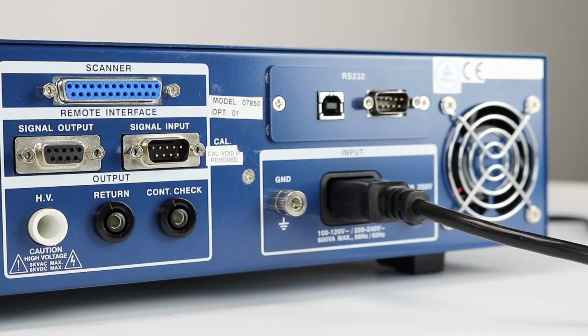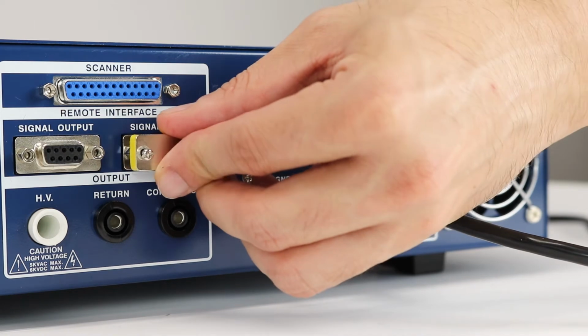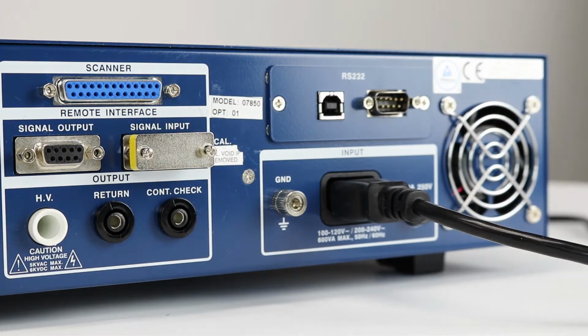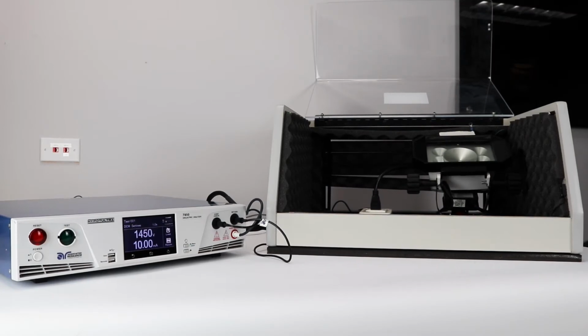Insert the remote interlock key into the signal input terminal on the rear panel. The instrument will not output voltage without this key. This allows the user to wire the instrument to the doors of a DUT enclosure. This is a safe workstation best practice.